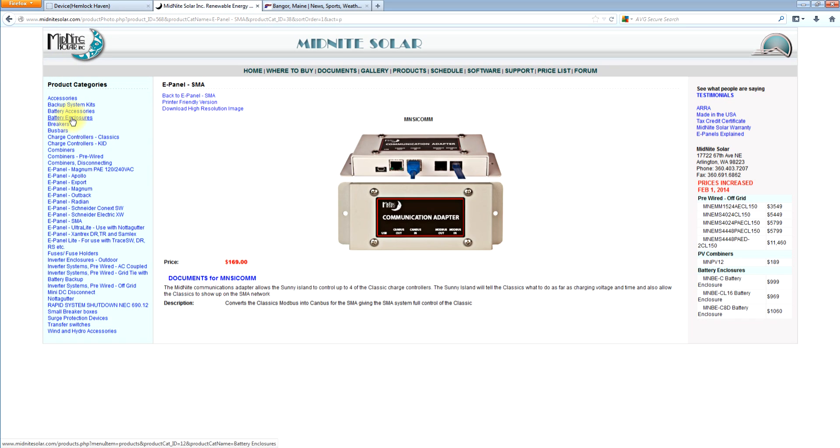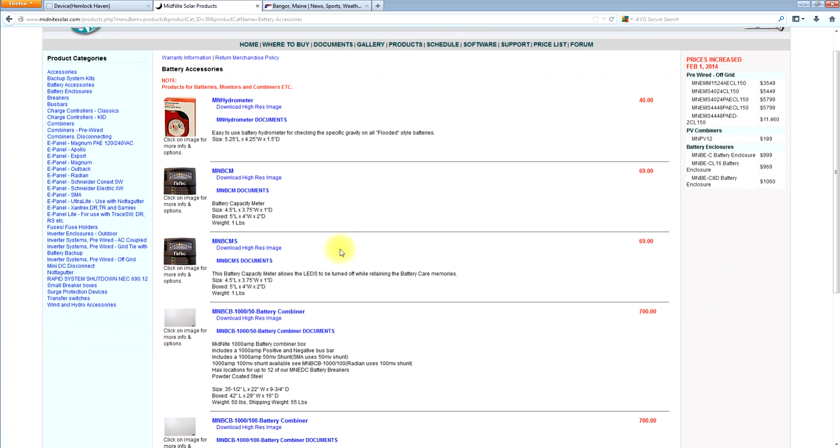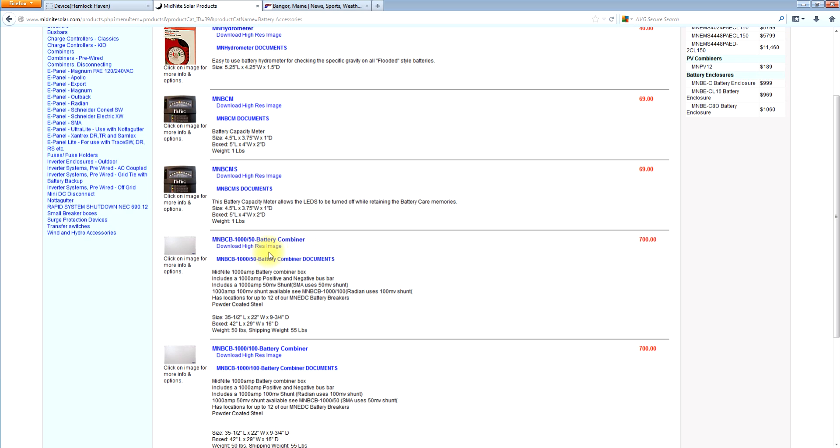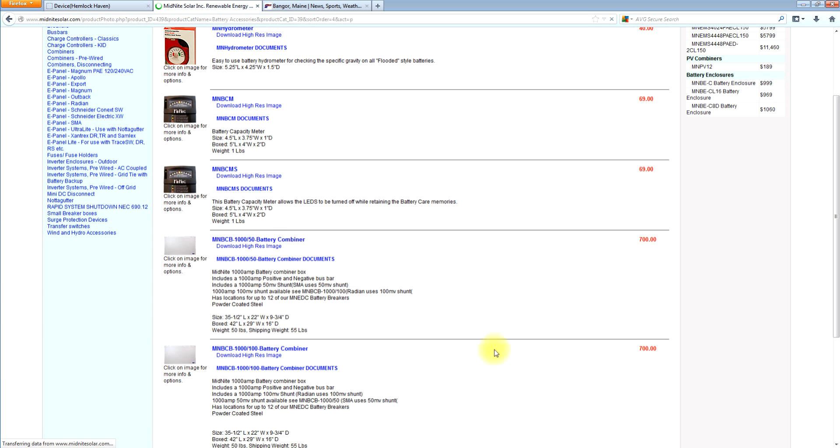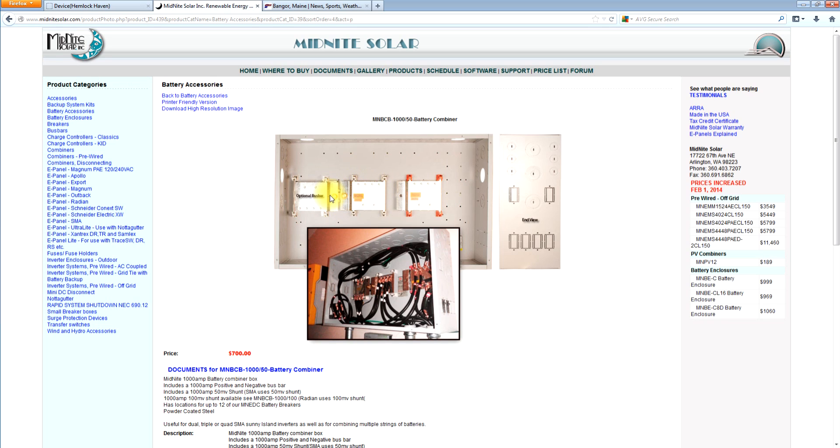I wanted to show you the actual battery combiner while I'm right here. So let's go to battery accessories and let's go to battery combiner. Which one do I need? The 50 millivolt. You'll notice we have a 50 millivolt and a 100 millivolt shunt. And basically what that boils down to is inside the box here. This one's shown with the optional bus bar which we'll talk about. But there's a 1000 amp shunt right here. So essentially what you'd normally do is come in with your battery strings and go out to your four Sunny Island inverters. And that way everything goes through the shunt.